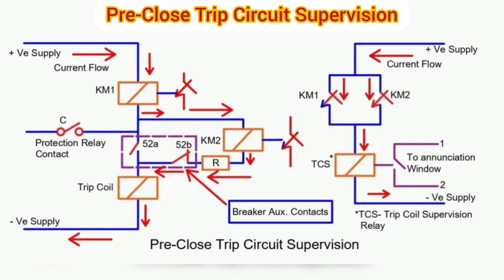Pre-close means breaker status before closing — the breaker is open. Thus the status of breaker contact 52A is open and contact 52B is closed. When the breaker is in open condition, current does not flow through 52A contact; instead, current finds its path through the breaker auxiliary NC contact, KM2 and KM1. Current flowing through KM1 and KM2 energizes both relays. The positive supply routes through the contacts of KM1 and KM2 and energizes the TCS relay. The NC contact of TCS becomes NO and no annunciation window glows, showing that the trip circuit supervision circuit is healthy.